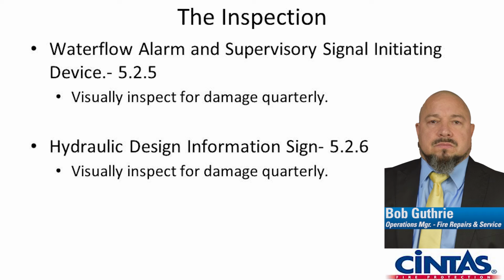The hydraulic calc plate, if you guys have buildings that you manage, anytime you're at your buildings, go and look at the riser, go and find this plate, take a picture of it, and store it somewhere. And then when we send you a quote to replace the hydraulic calc plate because it's not on site, we couldn't find the as-built drawings to get the information for it, we have to reverse engineer that system, meaning the original time, we have to try to recreate that, find the remote area, take a new water flow test from the street, from the city hydrants, and then calculate through the system to determine if the system with the current water pressure will still operate as it was initially designed. Depending on the structure, that can be very challenging and it's very expensive.